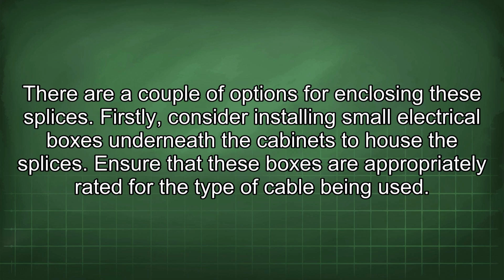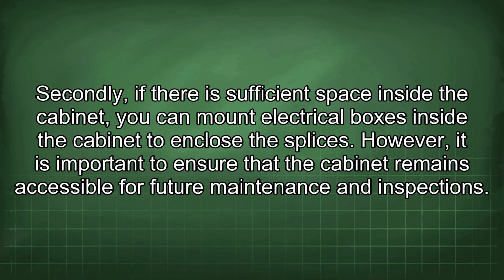Firstly, consider installing small electrical boxes underneath the cabinets to house the splices. Ensure that these boxes are appropriately rated for the type of cable being used. Secondly, if there is sufficient space inside the cabinet, you can mount electrical boxes inside the cabinet to enclose the splices. However, it is important to ensure that the cabinet remains accessible for future maintenance and inspections.